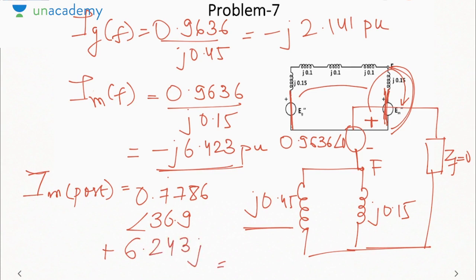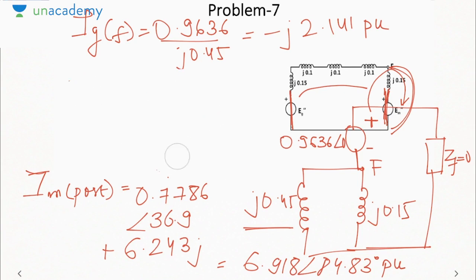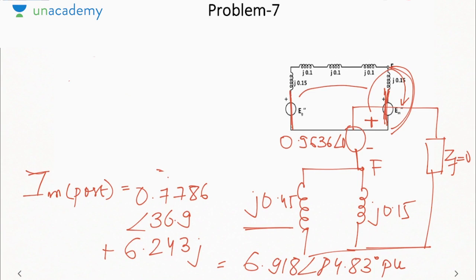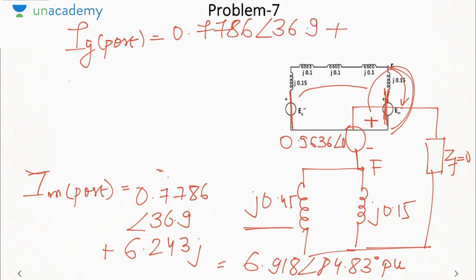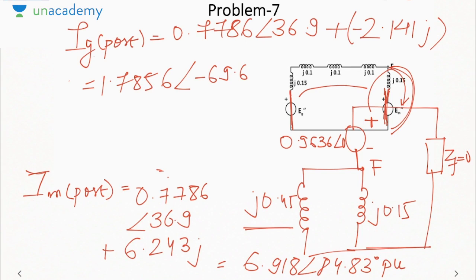So it will be minus 6.423 J. So this comes out to be 6.918 angle 84.83 degree pu. Similarly, if we talk about the generator, earlier also it was delivering the current, now also it is delivering the current. So I generator post fault will be 0.7786 angle 36.9 plus minus 2.141 J. We will have to add both the currents. So it will be 1.7856 angle minus 69.6 degree PU.